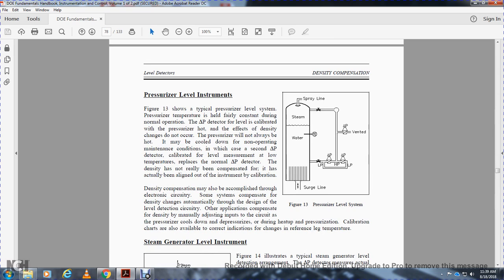Pressurizer level instrument. Figure 13 shows the typical pressurizer level system. Pressure and temperature are held fairly constant during normal operation. The differential pressure detector for level is calibrated for the high pressure and temperature condition. The effect of the density change is not compensated when the tank is cooled down during a non-operating maintenance condition, so the indication will read low with the normal differential pressure detector calibration. The density is not really compensated; it has actually been aligned out with the instrument calibration.